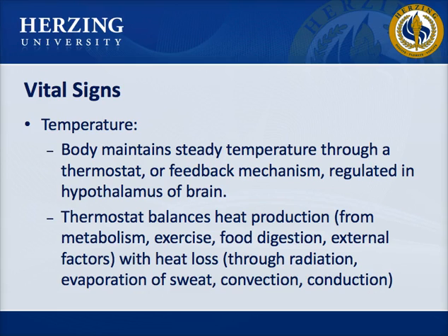The tympanic route senses infrared emissions of the eardrum, so it is an accurate measurement of core temperature. The temporal artery thermometer uses infrared emissions from the temporal artery and provides an average of multiple readings. There are conflicting reports regarding the accuracy of the temporal artery thermometer.